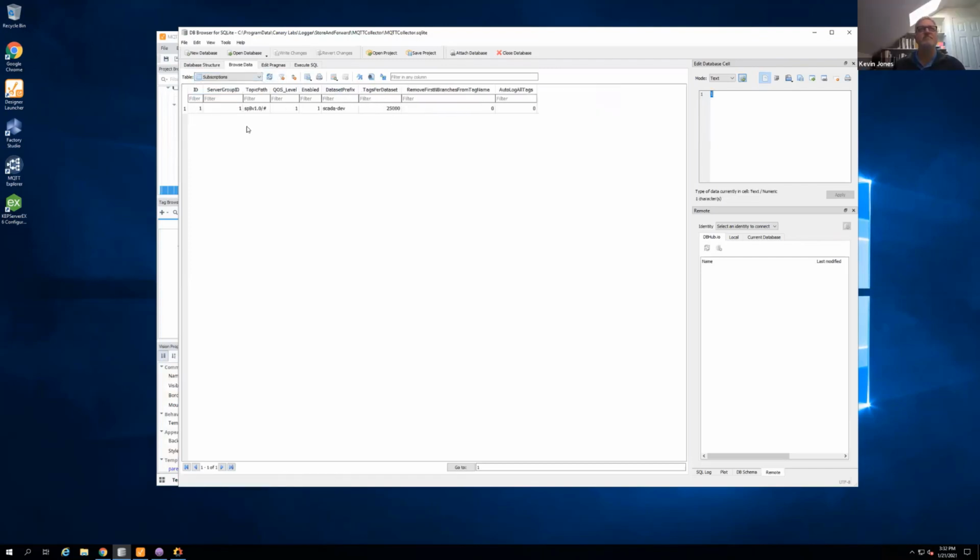And so then here's what we're going to subscribe to. The topic path itself, and this is where you would limit what it is that you want to subscribe to in your historian on the historian node. So again, everything publishes to the unified namespace, and now you become a receiver of that information. You're a subscriber to whatever that information is. And within the Canary historian, I can limit to exactly what it is that I want to bring into my historian. So I'm going to set this to where it's now going to auto log all the tags.